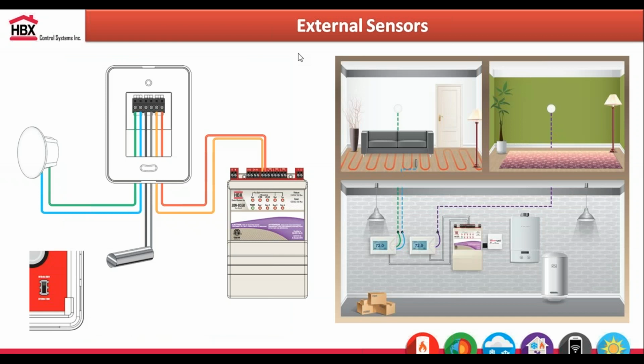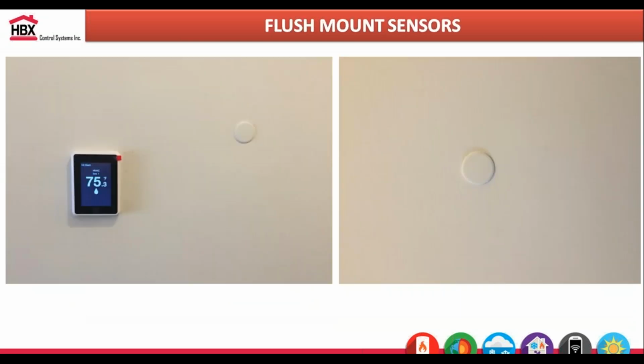In terms of external sensors, for the bigger jobs that we do, we're doing a lot of these big 16, 17 zone systems, and the customers don't want 16, 17 thermostats spread out throughout the home. So another option is to put all the thermostats in the mechanical room and just run sensors throughout each zone. So you still could do the air and the floor. That's why we have the ability to run up to 2 sensors per stat.